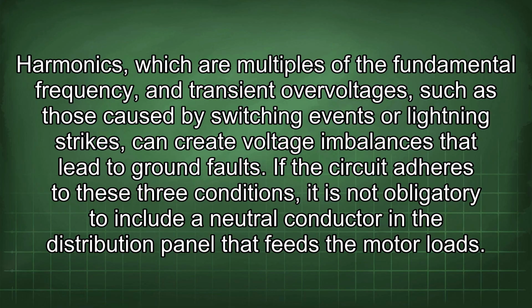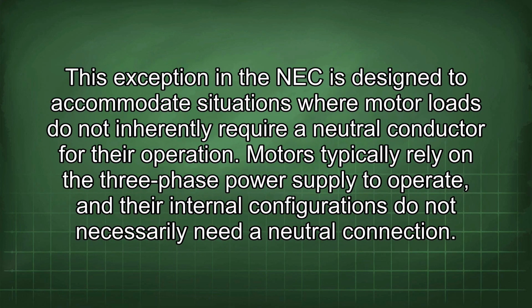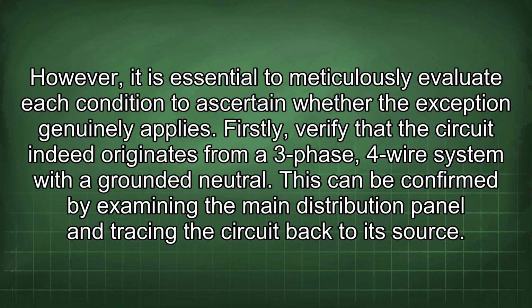If the circuit adheres to these three conditions, it is not obligatory to include a neutral conductor in the distribution panel that feeds the motor loads. This exception in the NEC is designed to accommodate situations where motor loads do not inherently require a neutral conductor for their operation. Motors typically rely on the three-phase power supply to operate, and their internal configurations do not necessarily need a neutral connection. However, it is essential to meticulously evaluate each condition to ascertain whether the exception genuinely applies.